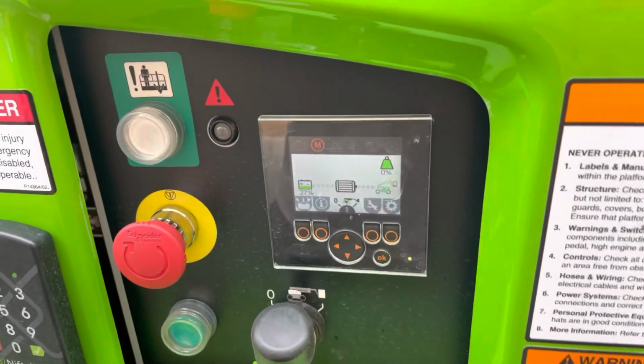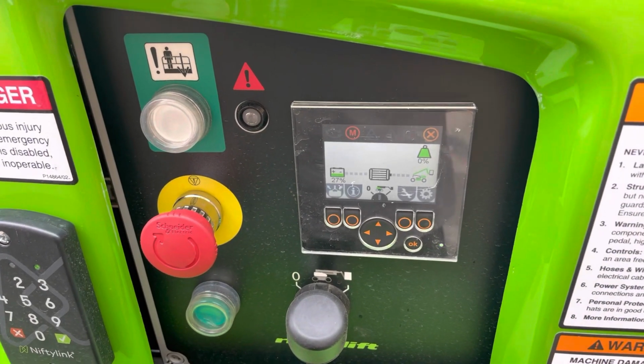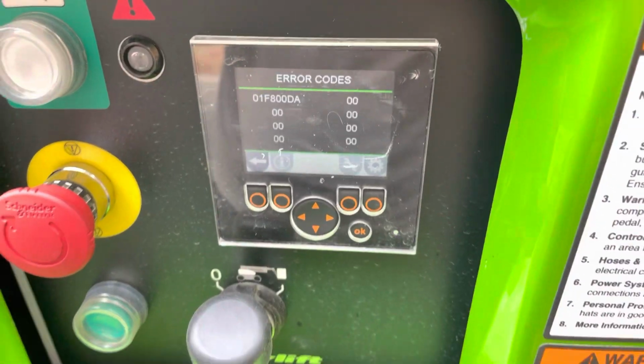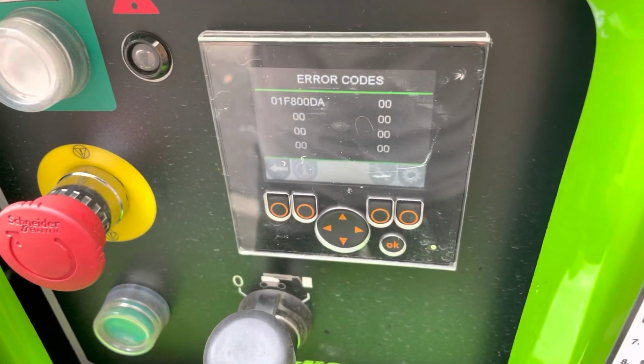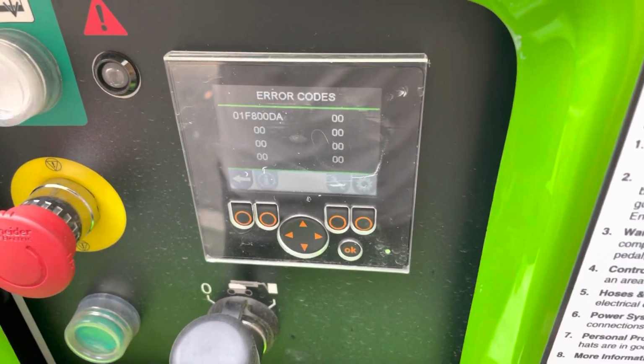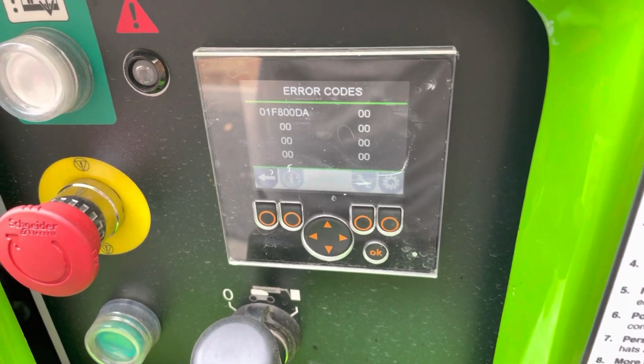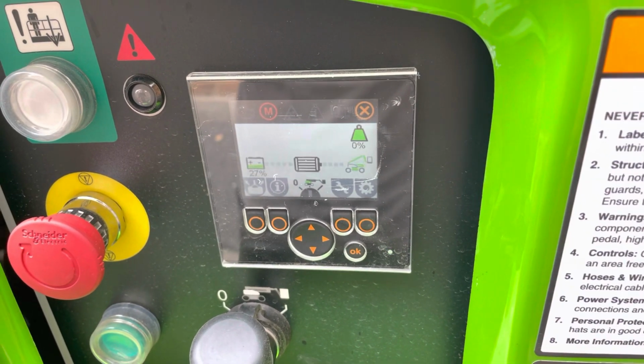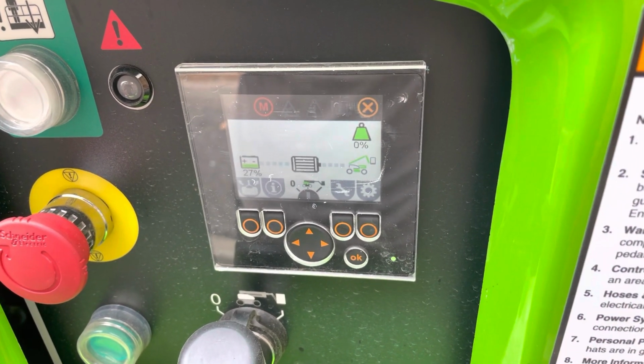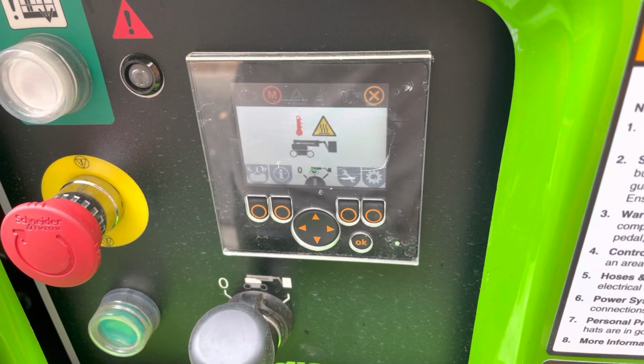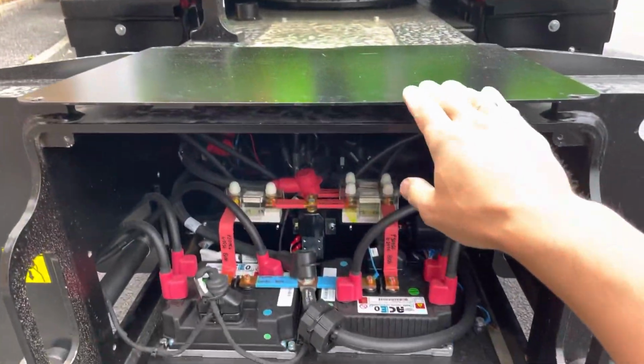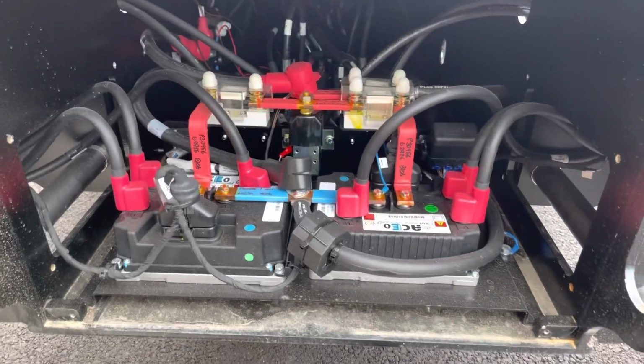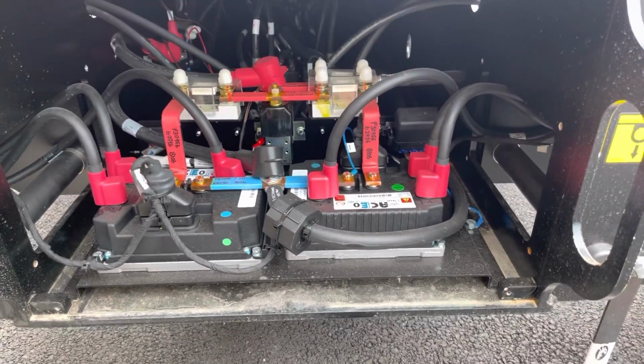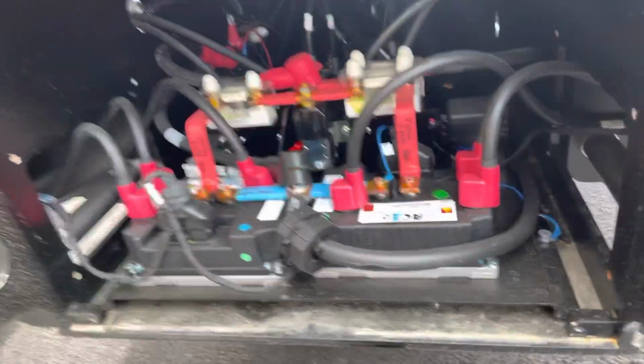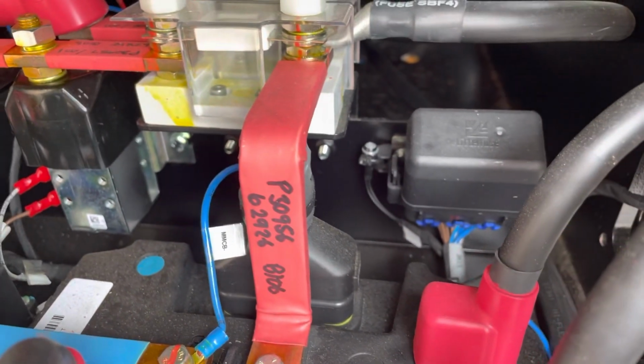So we're gonna try to look into error code to see what that means, and we're gonna try to deal with that. So that error code means that the master drive controller has overheat error. So it's either very hot or is the fault with the temperature feedback. So take the cover off and you will find the two drive controllers. Okay, so one is master, one is slave, and there is LED flashing here as well. So that LED should be flashing the error code as well.